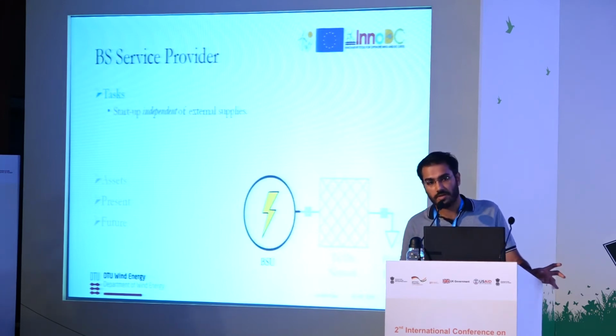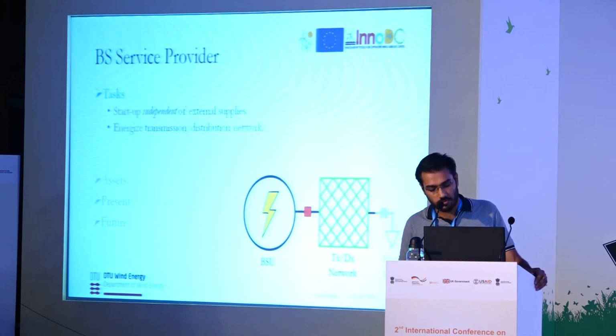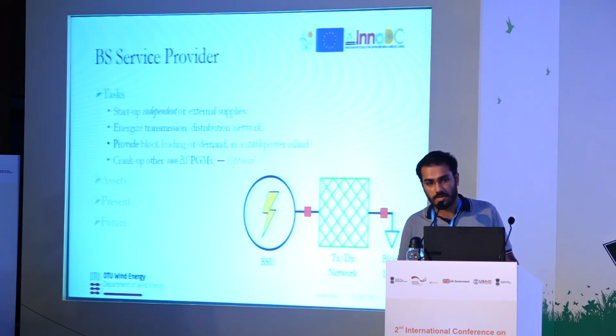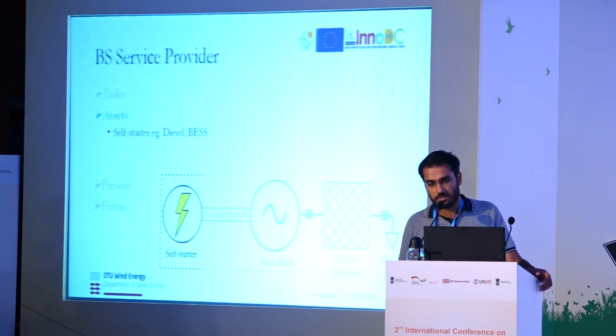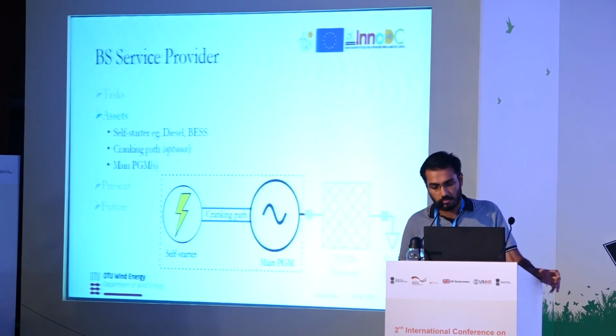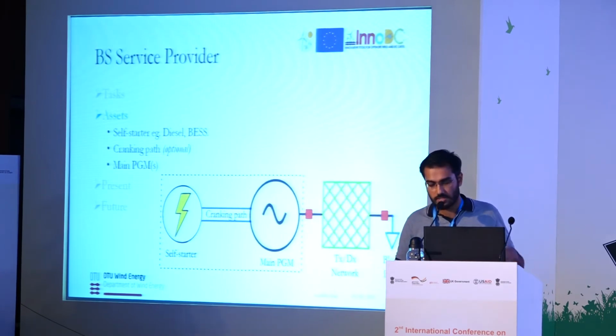So a Blackstart service essentially has 3 tasks, which is to start up independently of external supplies, then energize the transmission and distribution network, and then provide block loading of the demand. Most of the time it also provides auxiliary supply to the non-Blackstart power generation modules. It consists of a self-starter, which is typically a diesel or battery energy storage system, and a cranking path, which may be optional if the self-starter is co-located with the main power generating module. That is the generator that takes up the responsibility of ultimately energizing the transmission system and then dealing with the megawatts and megavars of power flow. And each stage has different technical challenges, which I'll be talking about very soon.